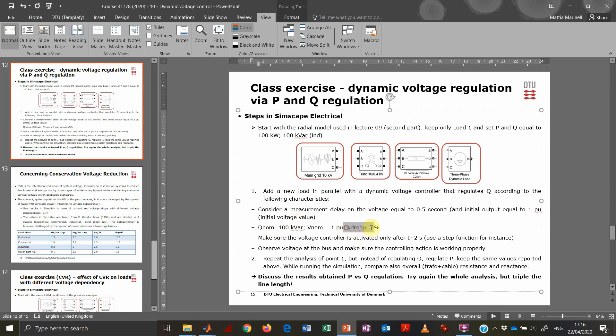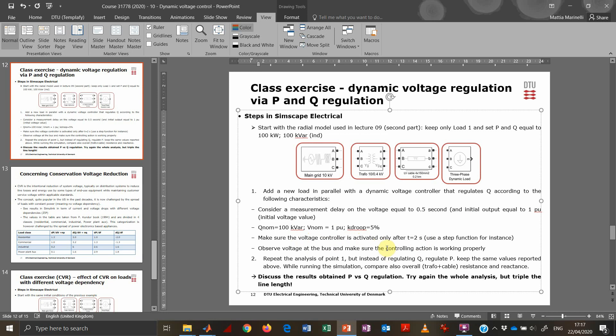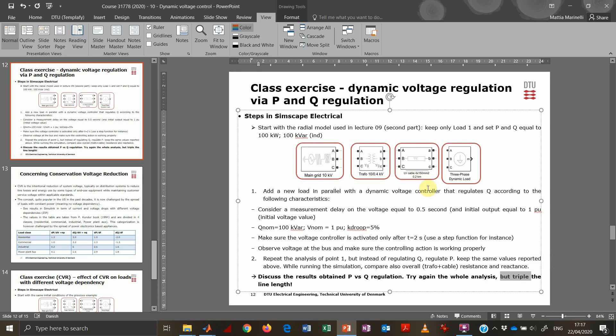The controller parameters: it should be a droop of 5%. The unit we want to control should be a 100 kVAR reactive unit that we can adjust. Since we are discussing increasing the voltage in a loaded situation, we will deploy capacitive power. We want to activate the controller just after two seconds. Then we repeat the analysis but instead of regulating reactive power, we modulate active power and compare the results. As a last point, we redo the same analysis but with the cable three times longer - this one is 200 meters, so we'll replace it with a 600 meter cable.